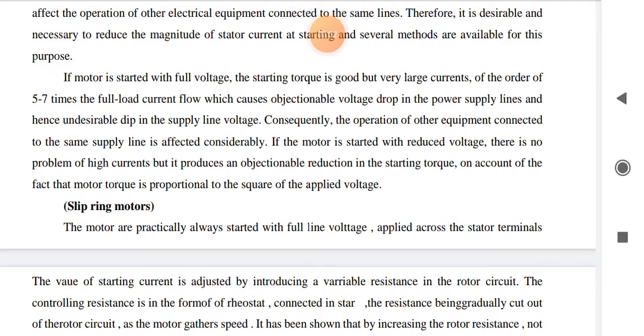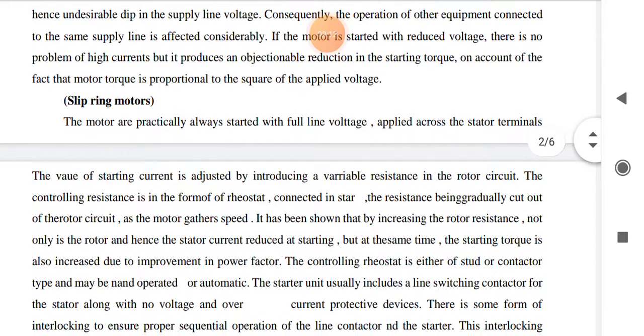If the motor is started with reduced voltage, there is no problem of high current, but it produces an objectionable reduction in the starting torque on account of the fact that motor torque is proportional to the square of the applied voltage.